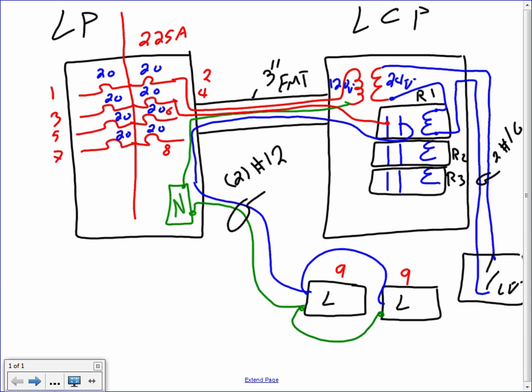Let's see how this works. When you turn this, can you see the 24 volt coming right here? When you close this low voltage switch, you bring the 24 volt and put it across the coil. When you put the 24 volt across the coil, the contactor shoots closed, and these lights go on. This is the concept of a low voltage lighting control system.